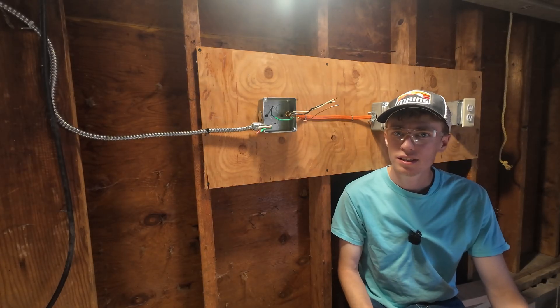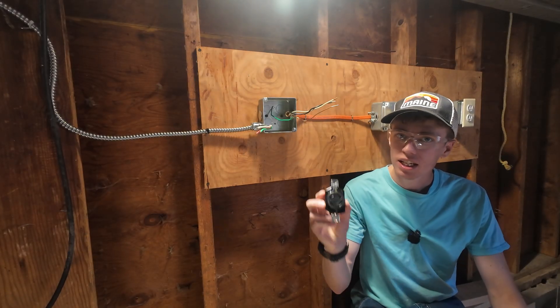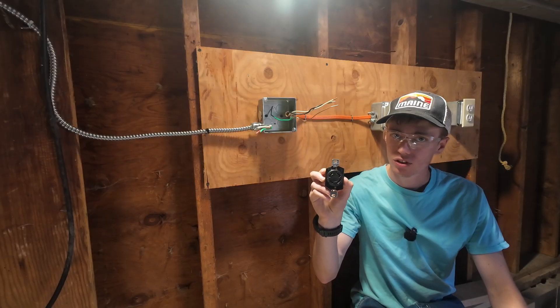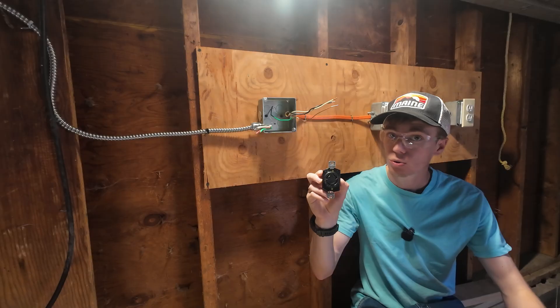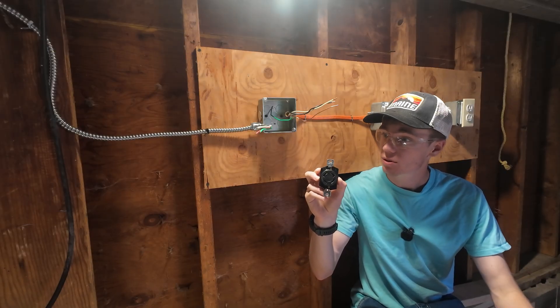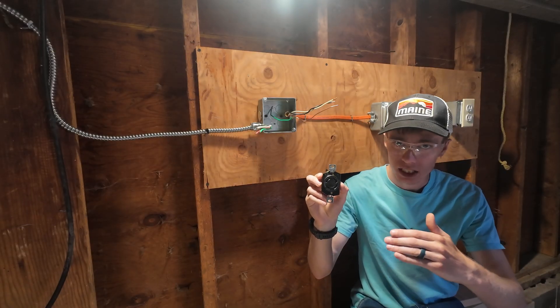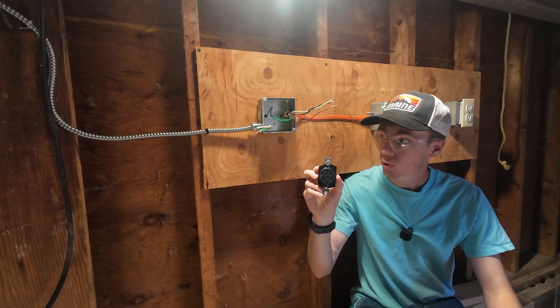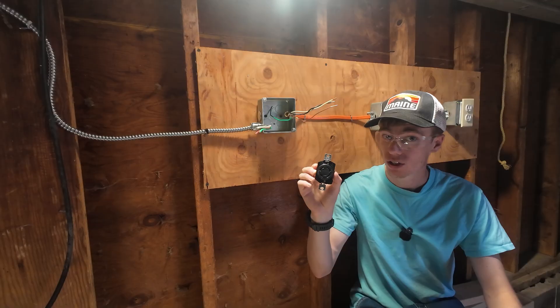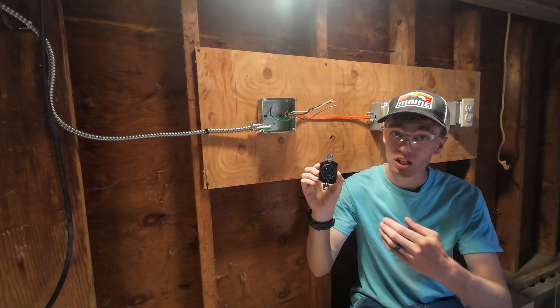Welcome back to another episode. Today we're going to be installing a NEMA L14-30. That is a 125/250 volt receptacle — the reason I say 'slash' is because it has the ability to pull both 120 volt power and 240 volt power, because there is a neutral reference.